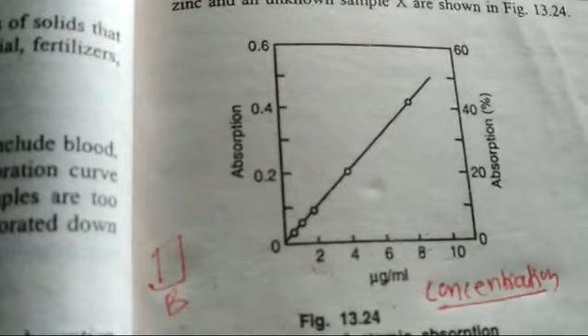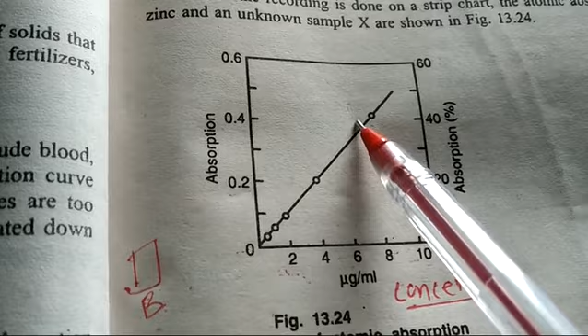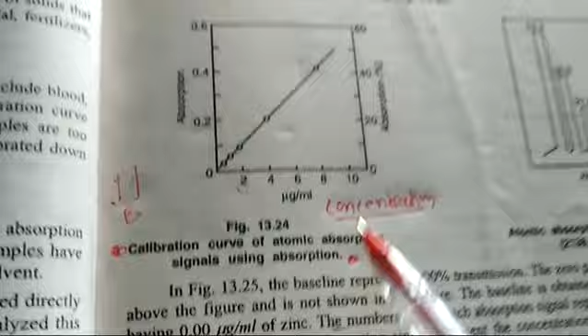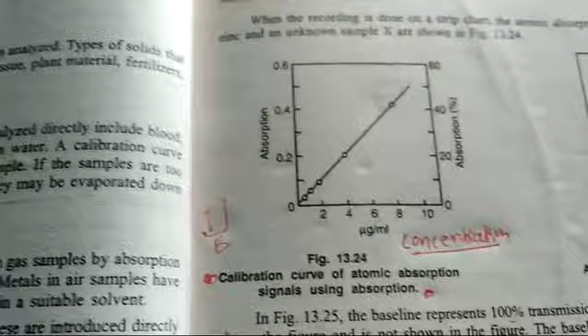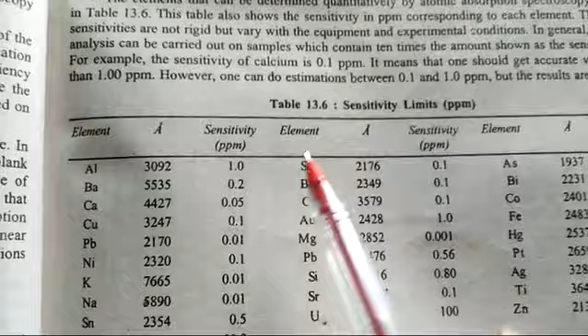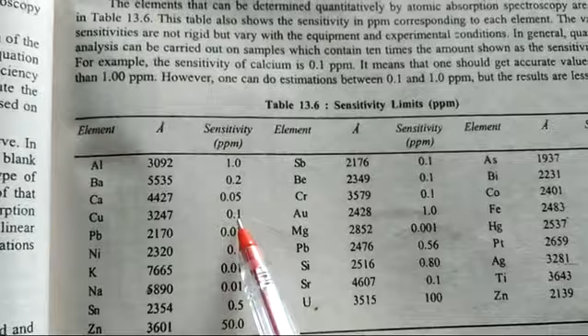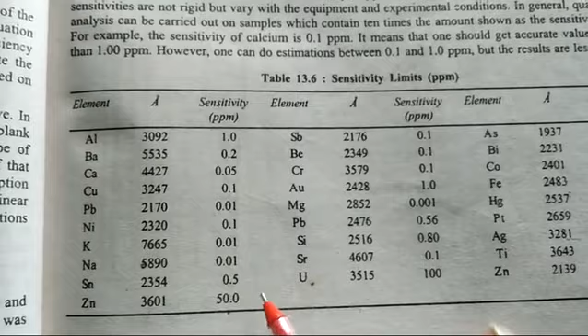On one side is the concentration and on the other the absorbance. Here are the known concentrations. At 2 microgram per ml concentration we receive this, and at 4 microgram per ml concentration we receive an absorbance of 0.2. So these are the known concentrations. Then we put in the unknown solution and find its concentration. So this is the calibration curve method. The sensitivity limits are: aluminium up to 1 ppm, barium 0.2 ppm, calcium 0.05 ppm, copper 0.1 ppm, nickel 0.1 ppm, and zinc near about 50 ppm. So this is the sensitivity.